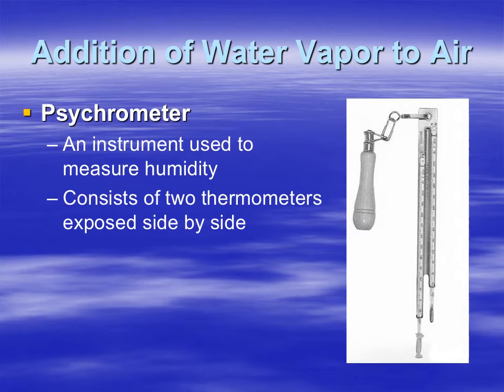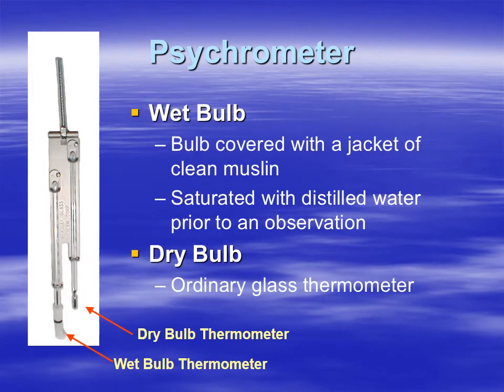The psychrometer is made up of two thermometers side by side, exposed to the air. One thermometer is called the wet bulb — it has muslin fabric at the bottom, saturated with distilled water, to ensure the water is pure. The other thermometer has no muslin and is called the dry bulb — it's basically an ordinary glass thermometer.